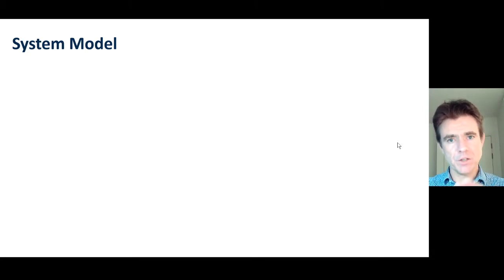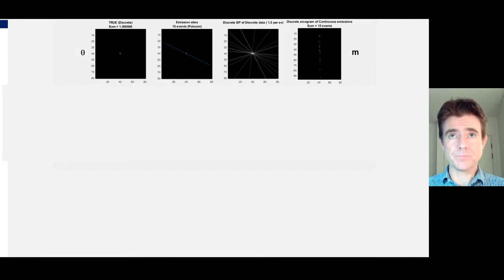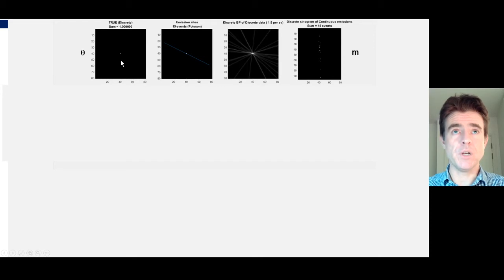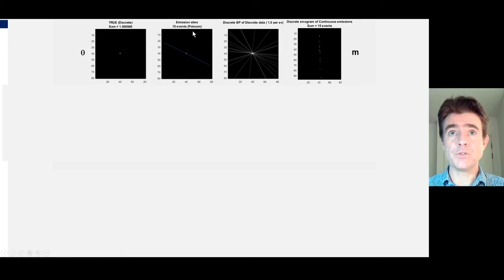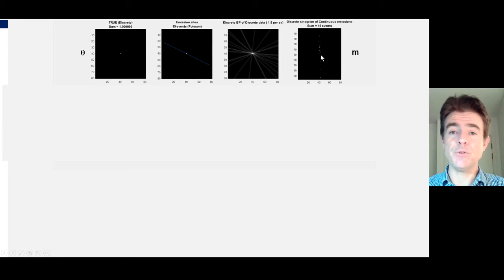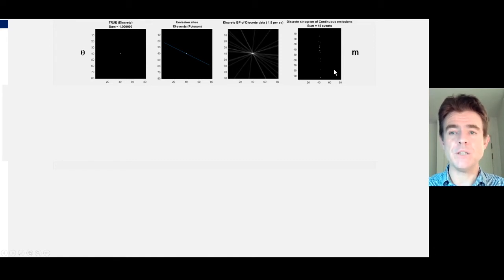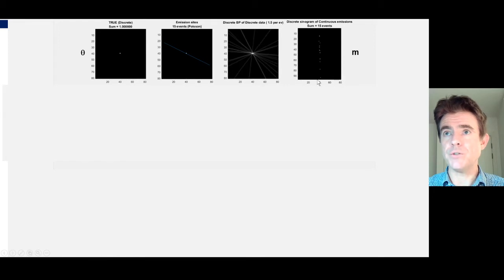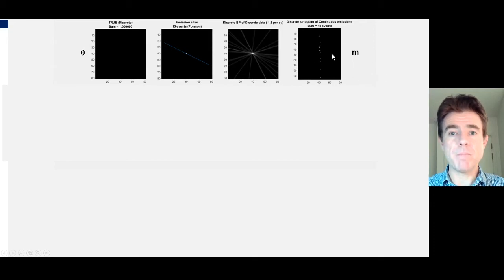The focus now is on the system model — how we get from a parameter vector to a model of the mean. Here is an example of how we would model the mean of the data. Here's a point source inside a PET scanner field of view, and I'm showing example back-to-back photon pairs shown by those blue lines. This shows the build-up of data counts being histogrammed into a sinogram, where this is the radial distance of a line and that's the angle of the line — so that's going to be called sinogram M.